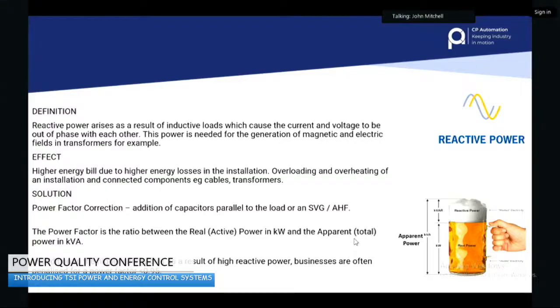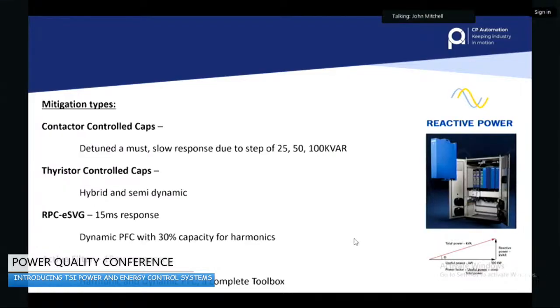But there are things to be considered, and that is there are different types to improve power factor. If a customer has old power factor correction installed, they would typically have upgraded to VSDs, variable speed drives, at some point. Variable speed drives and old power factor correction do not like each other, they are not friends. The reason is that capacitor banks are a sink for harmonics, and the variable speed drives create harmonics.